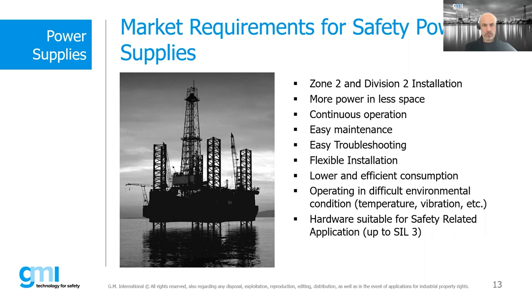To allow this installation in a certified area, the GMI power supply system has been certified for Zone 2, Division 2 installation, and offers the possibility to disconnect a module without interrupting the normal operation. This functionality is ensured by the hot swapping system, which each rack of the power supply system can be equipped with. Not having the hot swapping capability means that the final user must install additional circuit breakers certified for Zone 2, Division 2.